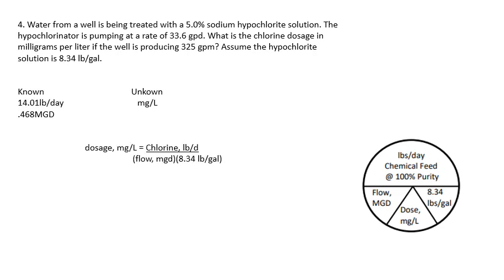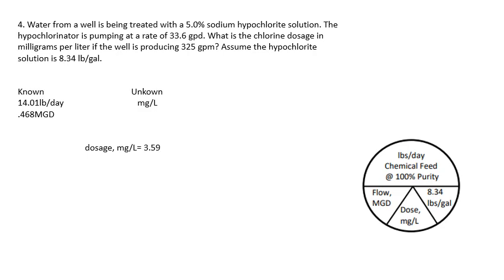That becomes our known. Now we know the pounds per day and the million gallons per day, so we can solve for dosage in milligrams per liter using the Davidson pie chart: 14.01 pounds per day divided by 0.468 MGD times 8.34 pounds per gallon equals 14.01 divided by 3.90. Your answer is 3.59 milligrams per liter.